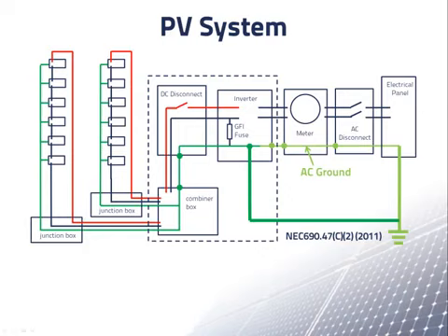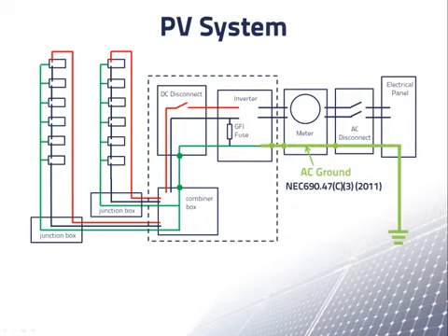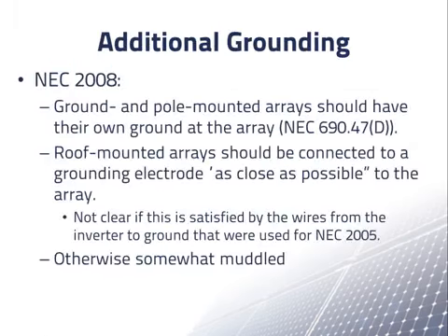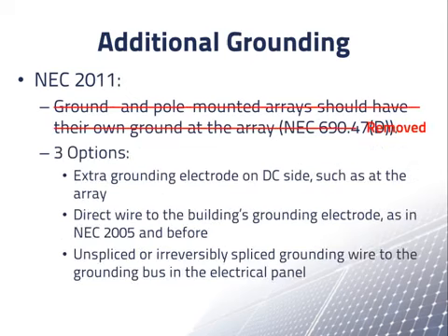Lastly, if nothing else is feasible, you are allowed to use the AC equipment grounding conductor to the electrical panel as your only grounding connection. However, this AC equipment grounding conductor has to be unspliced. This means that it has to be a single continuous wire with no screw or twist connections along the way. Permanent crimps and soldered connections are permitted. We show here the 2008 NEC grounding requirements. You may wish to stop the video to read them. This spells out the grounding requirements in the 2011 NEC for you to read.